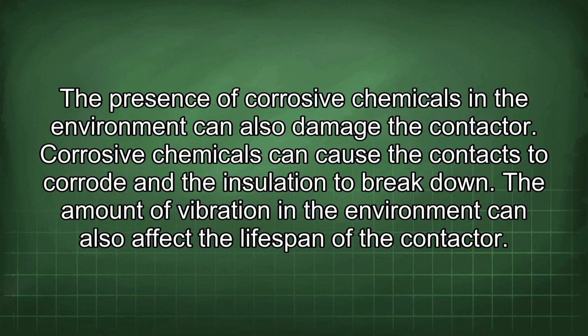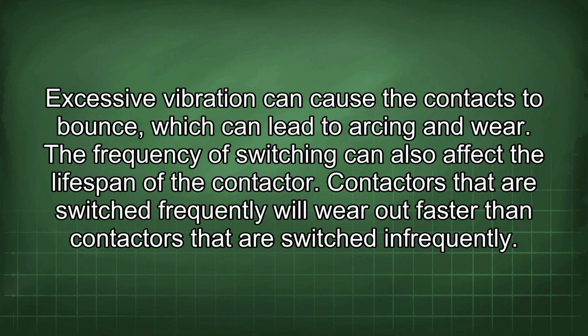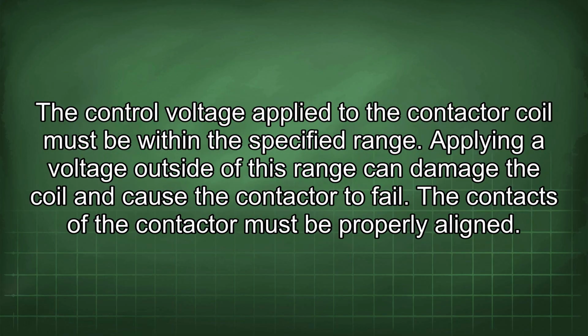The amount of vibration in the environment can also affect the lifespan of the contactor. Excessive vibration can cause the contacts to bounce, which can lead to arcing and wear. The frequency of switching can also affect the lifespan of the contactor. Contactors that are switched frequently will wear out faster than contactors that are switched infrequently. The control voltage applied to the contactor coil must be within the specified range. Applying a voltage outside of this range can damage the coil and cause the contactor to fail.